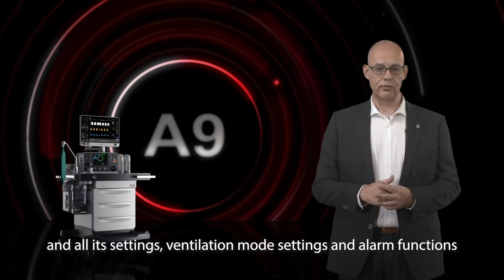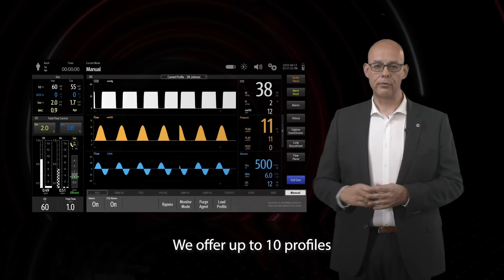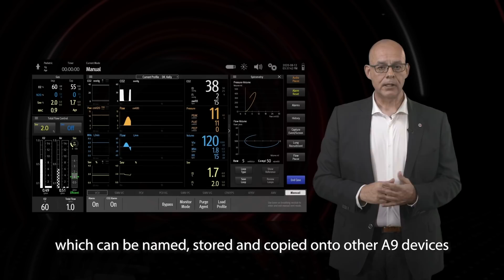The A9 has the possibility to customize the display and all its settings, ventilation mode settings and alarm functions according to the preferences. We offer up to 10 profiles, which can be named, stored and copied onto other A9 devices. And this helps you to find required settings fast and safe without losing much time, instead of setting all parameters individually every time with the risk of making mistakes.